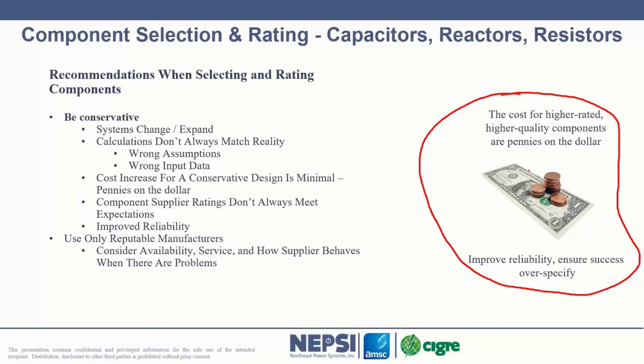You want to always be very conservative with the design, and it's really a cost of pennies on a dollar. You're already buying reactors, you're already buying capacitors, you're already buying resistors. It does not cost much more to say, well, I want a higher voltage rated capacitor. I want a more current rating in my iron core reactor. I want more higher watt rating in my resistors. And you do that, and it costs you maybe 10, 20, 30%. But what it does is it creates a very reliable system.